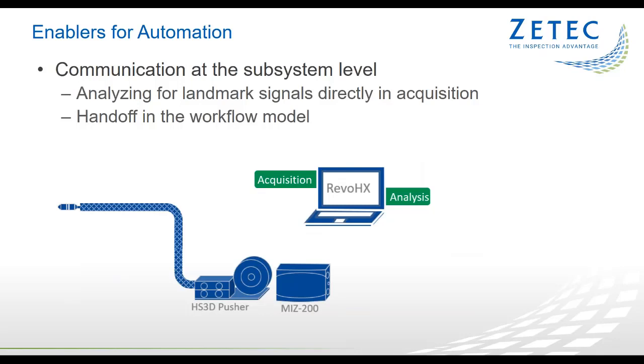One of the key integration features is landmark analysis directly within the acquisition module of the software. The ability to identify landmarks during acquisition allows for the programming of events to be triggered based on the position of the probe within the heat exchanger tube.